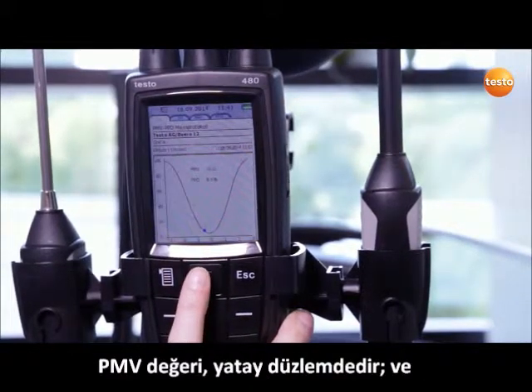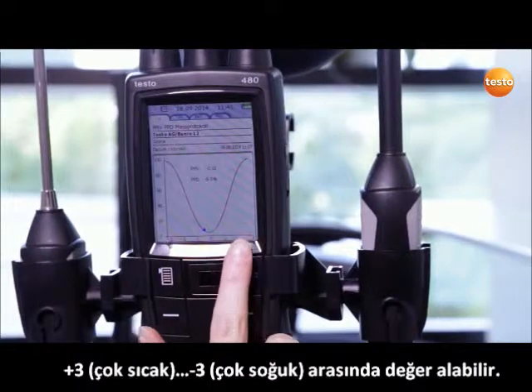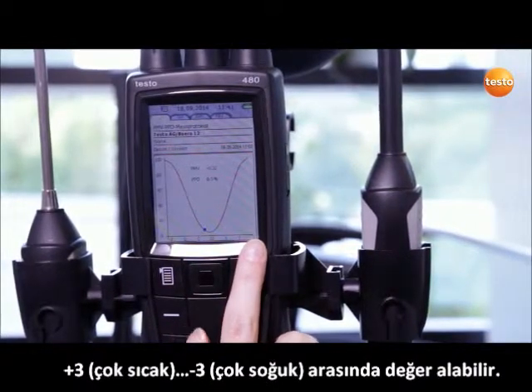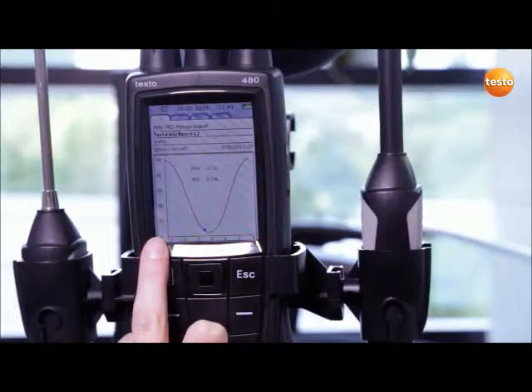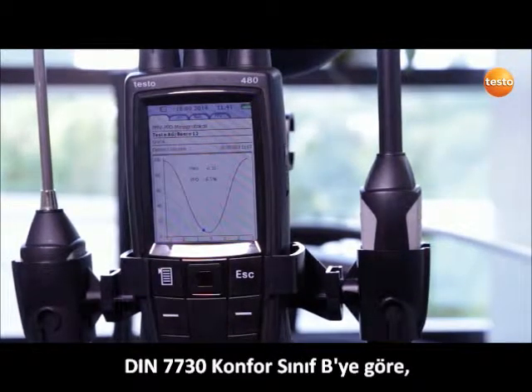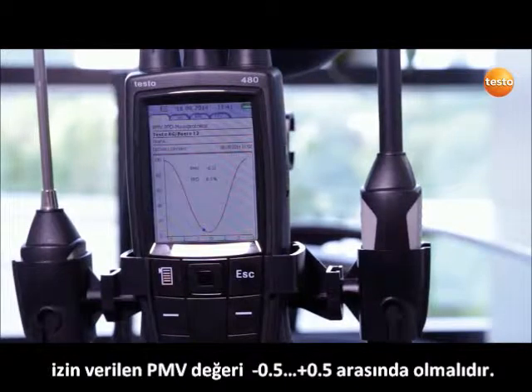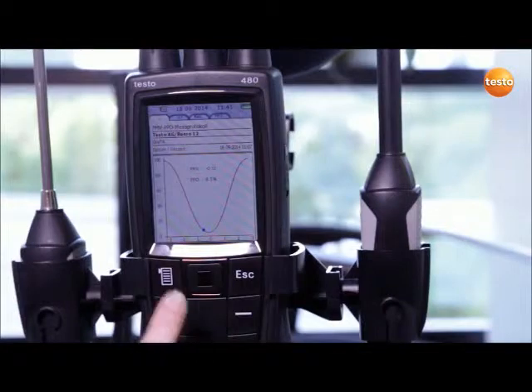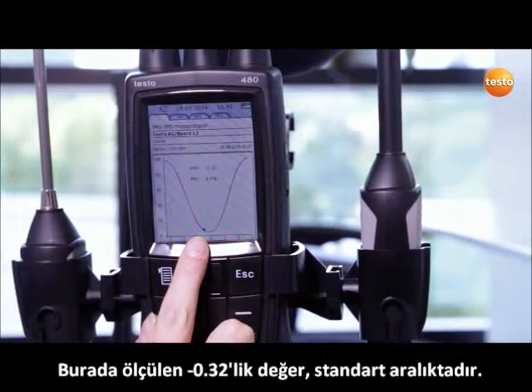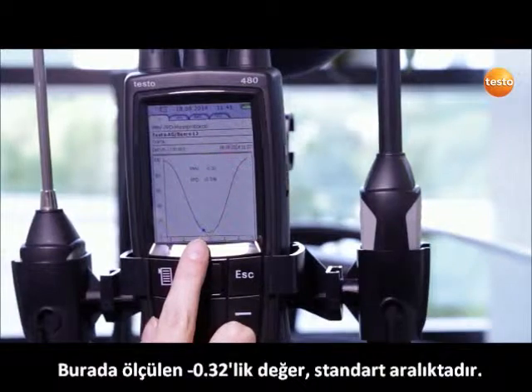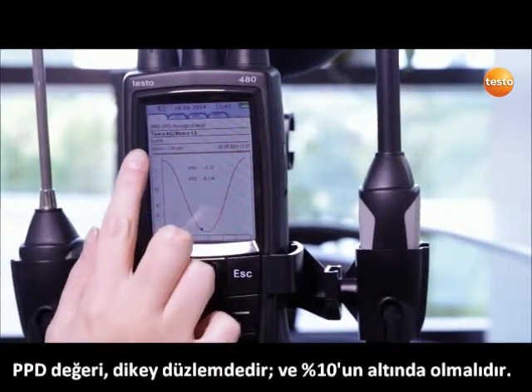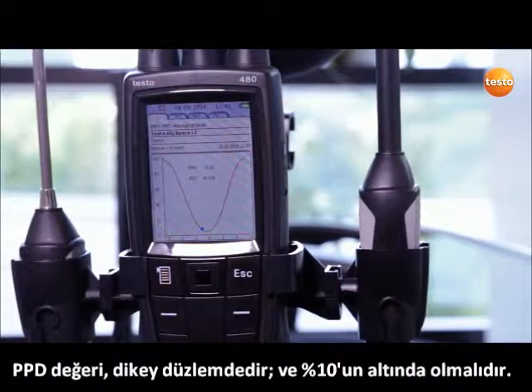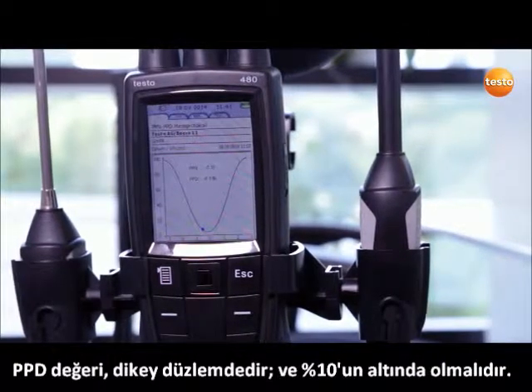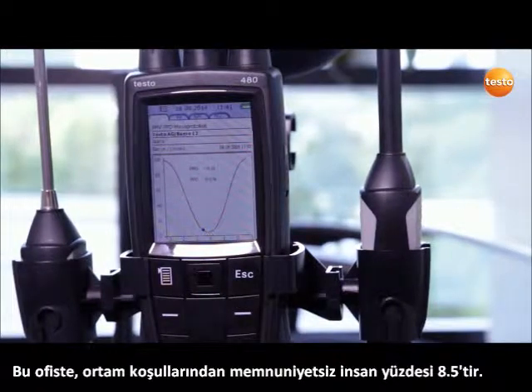The PMV value is shown on the horizontal axis and can vary between +3, which is too warm, and -3, which is too cold. According to DIN 7730, Comfort Class B, the permitted PMV value may be in the range from -0.5 to +0.5. The value of -0.32 measured here is within the required standard range. The PPD value is presented on the vertical axis and should be smaller than 10% in order to be within the standard range. In this office, we have a percentage of dissatisfied people of 8.5%.